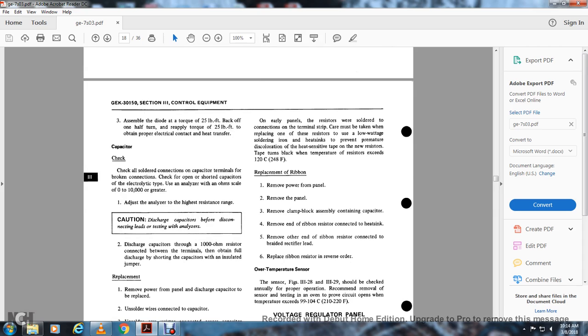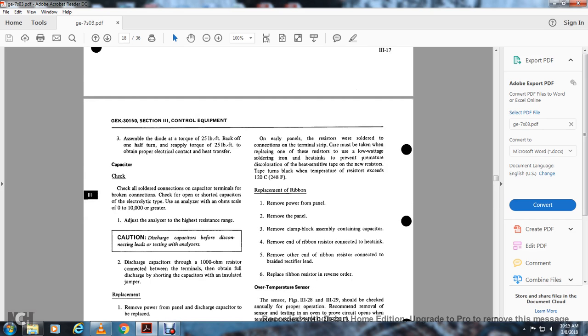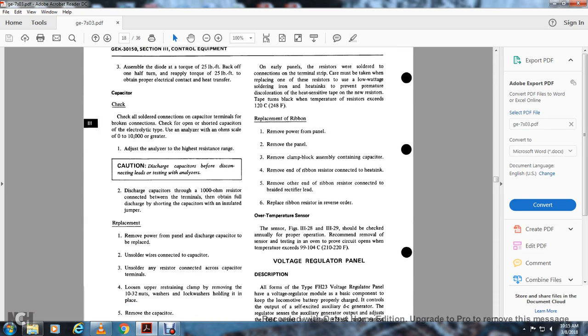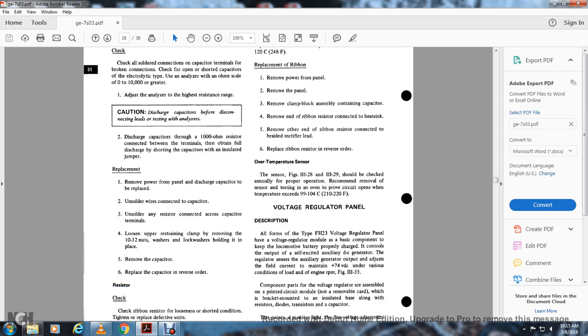Assemble the diode with a torque of 25 pounds. Back off the torque by one half turn, then reapply the torque to 25 pounds. The torque obtains the proper electrical contact and heat transfer. Check all soldered connections to the capacitor terminals for broken connections, and check the capacitor for opens and shorts with the analyzer on the ohm scale, 0 to 10,000. Check the analyzer on a high resistance range. Caution: discharge the capacitor before disconnecting leads and testing with the analyzer. Discharge the capacitor through a 1,000 ohm resistor connected between the terminals to obtain a full discharge, or by shorting the capacitor with insulated jumpers.